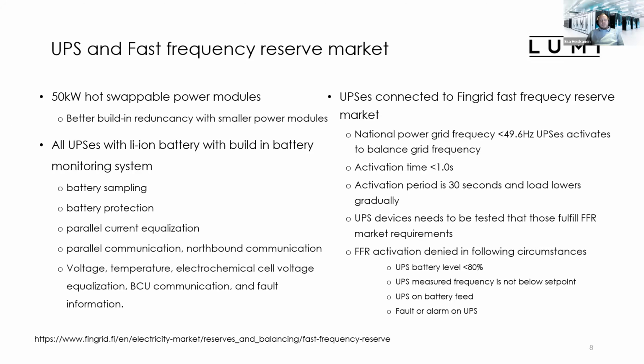And there are also some circumstances when this UPS activation to the fast frequency reserve market doesn't happen. This is so that we can keep our IT production safe in case there is an unbalance in the national power grid. For example, when the UPS battery level is below 80%, the activation doesn't happen.